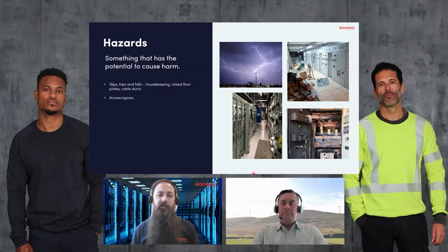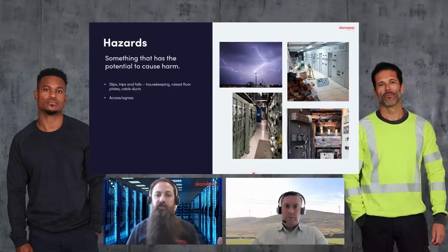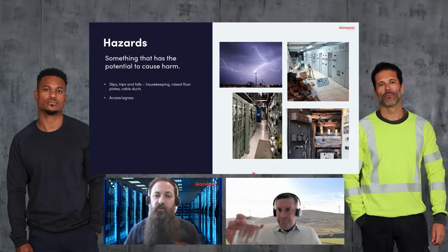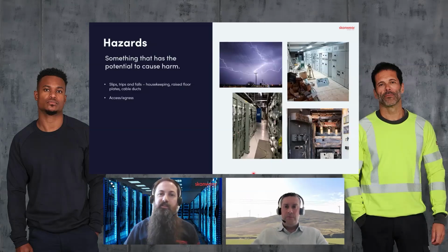Access and egress - someone mentioned it earlier, space is often at a premium. When we're building new factories, new substations, new data centers, where the switchgear is going is often not a massive consideration - it's just built against the design of what you've got. All the areas where VIPs go will be nice and spacious, but substation switchrooms and compounds are normally built to a size, more often than not to the design. The design often changes - we'll put a couple of extra panels on there for future use - so already you're limiting the space within there.